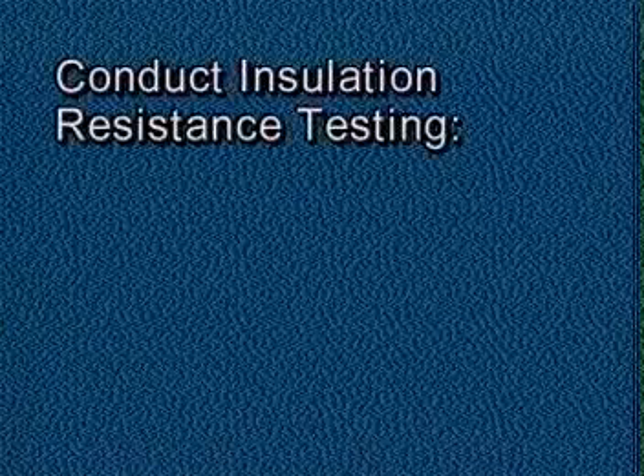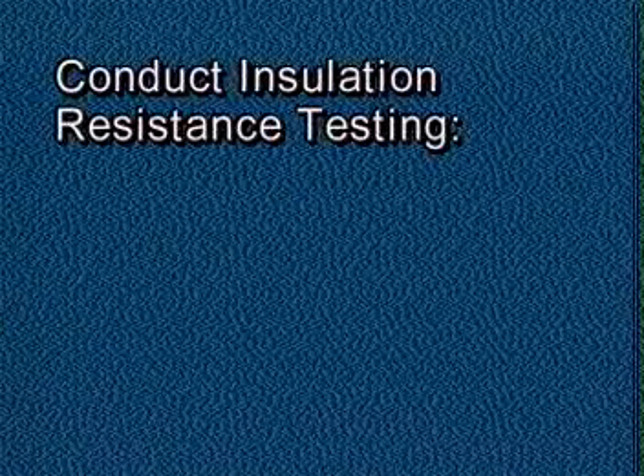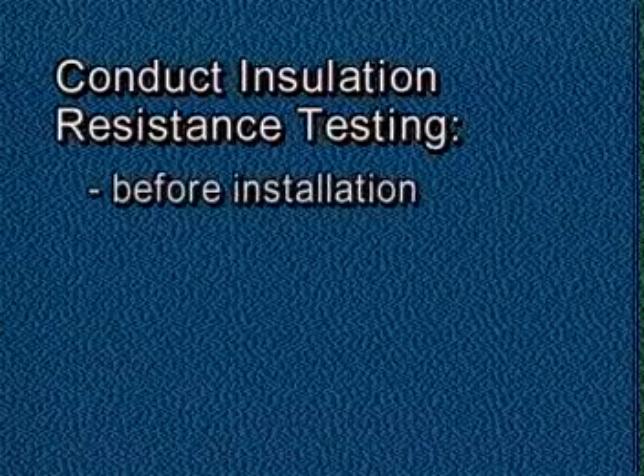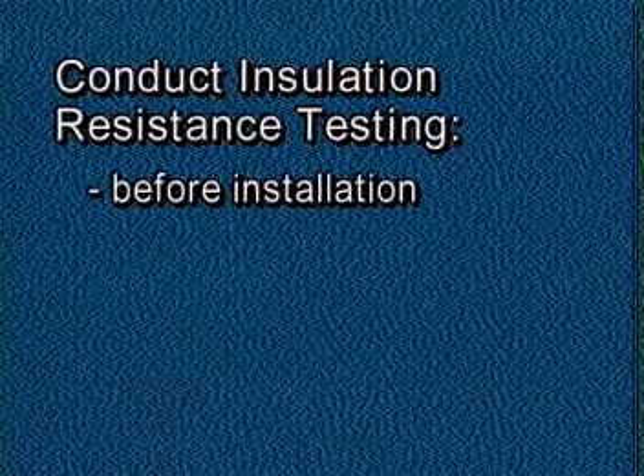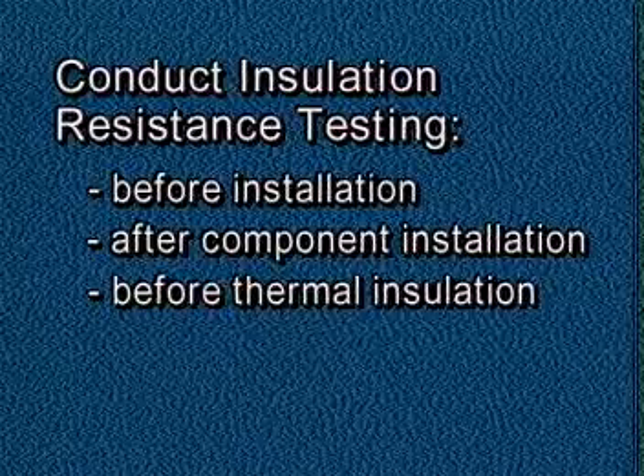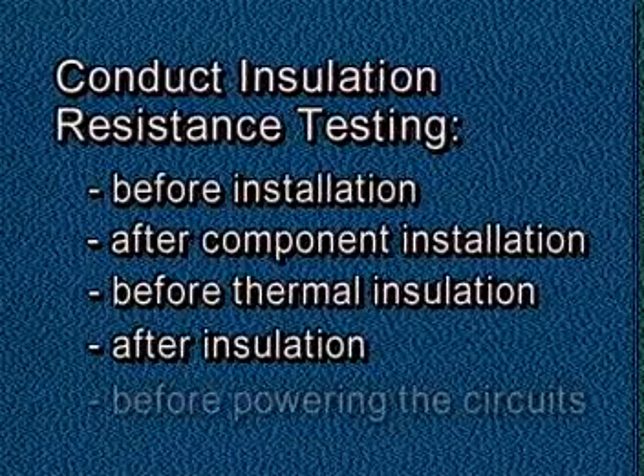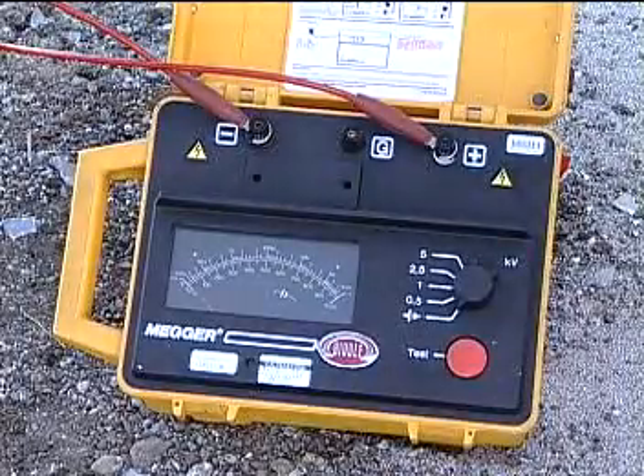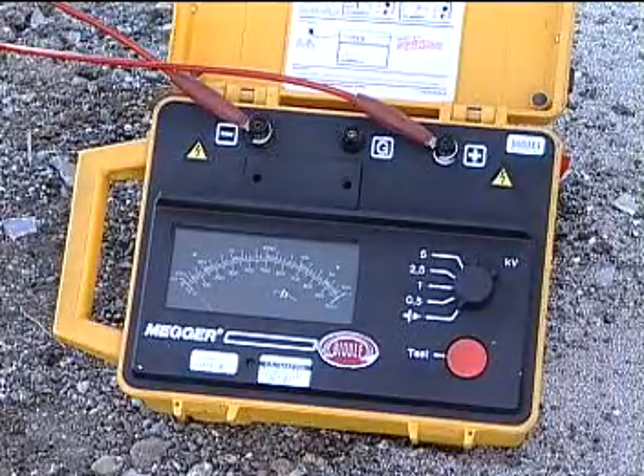Insulation resistance testing should be conducted several times during the installation process. Before installation, while the cable is on the reel, after component installation, before thermal insulation, after insulation, and before powering the circuits.